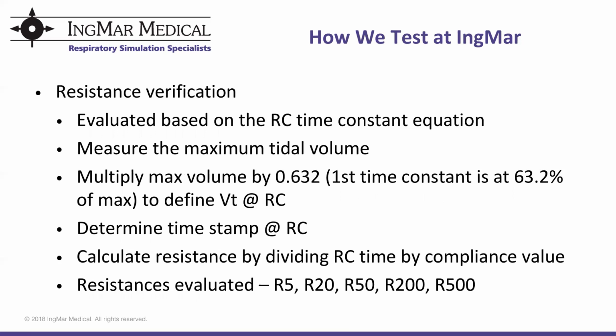The last test that we perform is called resistance verification. We evaluate our resistance based on the RC time constant equation. To determine this, we run a patient model with a set resistance value. The software feeds back the maximum volume for each excursion. We then solve for resistance based on evaluating the volume at 63.2% of its max using the equation resistance is equal to the time constant divided by compliance. The resistance range of the ASL 5000 is from 3 to 500 centimeters of water per liter per second. The resistances that we measure are R5, 20, 50, 200, and 500 during this test.